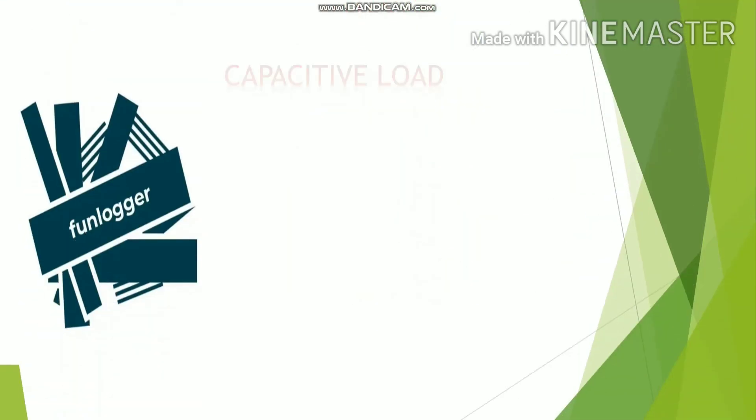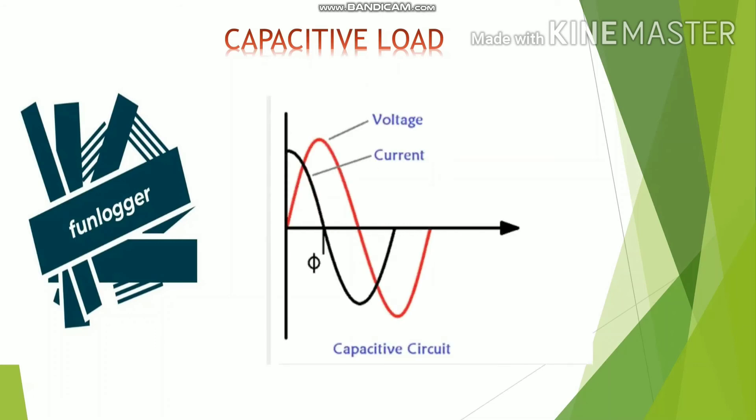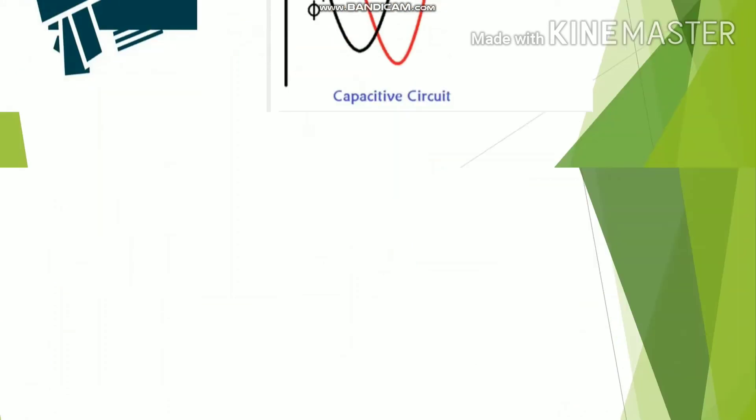The next one is capacitive load. Sometimes what happens is capacitive load gets increased while maintaining the inductive load at unity or near to unity, due to which current leads the voltage. This can be overcome by switching off one of the steps of the capacitor bank.